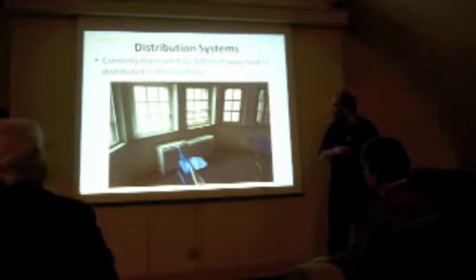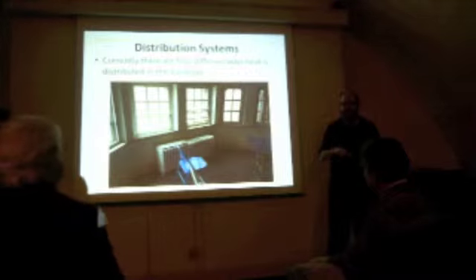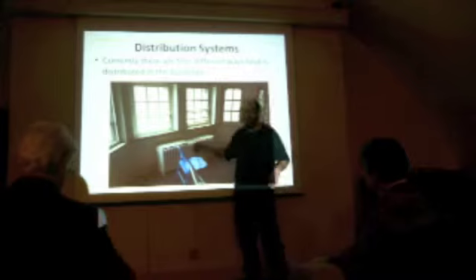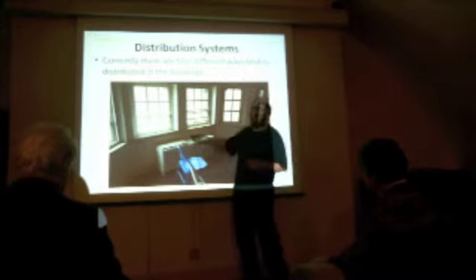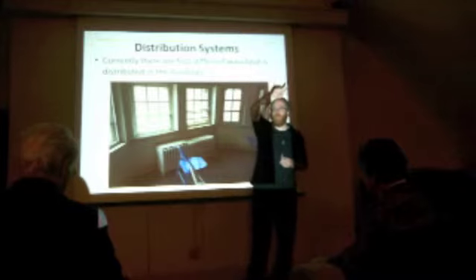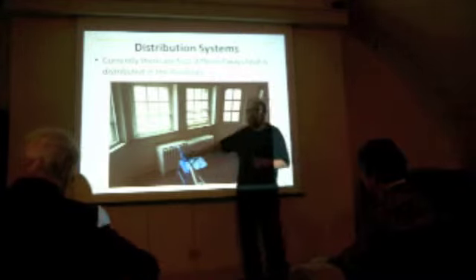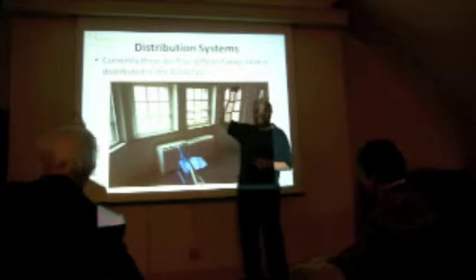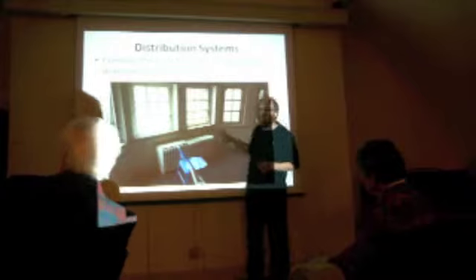And the cast iron? Well, yeah, I'll actually show you a couple of pictures. The cast iron ones, the reason that they're not more efficient is that the way that they're going to distribute the heat is to require a convection loop to form. So the warm air rises off of here, reaches the front of the room, which is colder, and cycles back through. But anything you put in the room, like the desks and chairs or people, disrupt that airflow. And so you get stagnant heat by the windows.